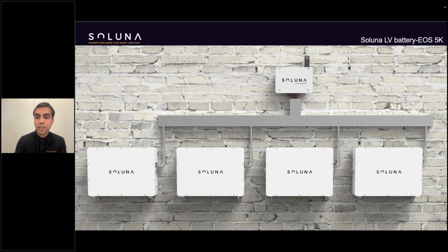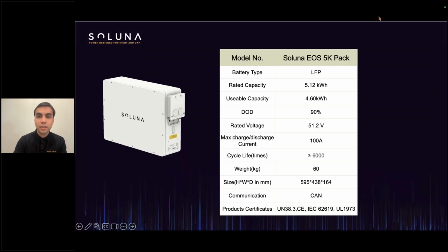Well, by now you will have more than just 4 connected to one parallel box. You can have up to 30 parallel batteries. This is the lithium battery with a rated capacity of 5.12 kilowatt hours, a usable capacity of 4.60 kilowatt hours, with a depth of discharge of 90%. The rated voltage is 51.2 volts, and the maximum charge is 100 amps, and the discharge current is also at 100 amps.